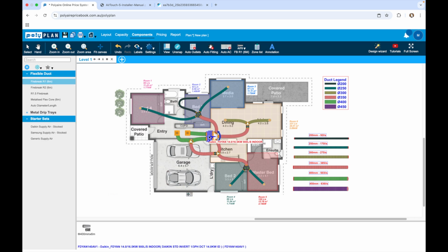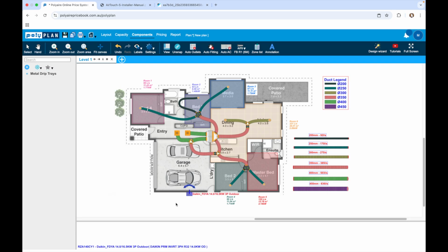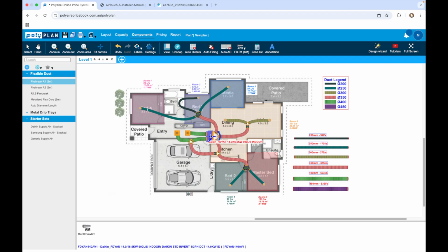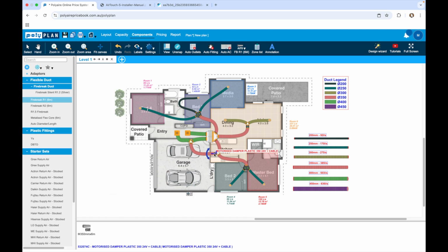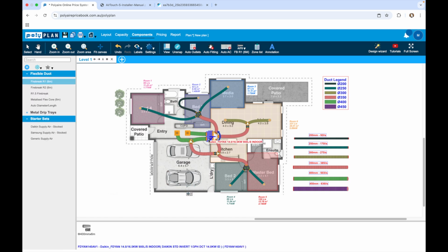This Daikin system itself has its own logic in there, where it's just looking at how cold a coil is in here, what your set point is, and what your return air temp is. Because this cold air is coming back through here and making this coil cold, this outdoor unit starts to slow down because it realizes it doesn't need to work so hard. And the more this starts opening, the colder this coil is able to be kept, and the more that this starts slowing down even further, until such a point that this is fully open and a lot of cold air is going back to this.